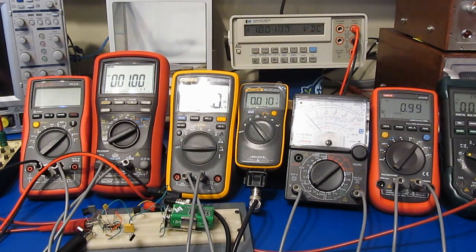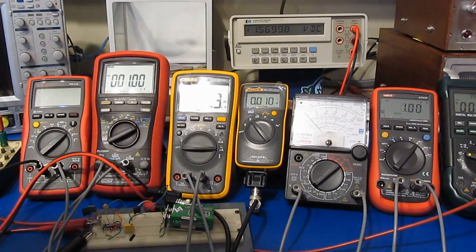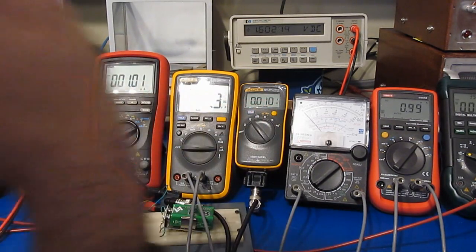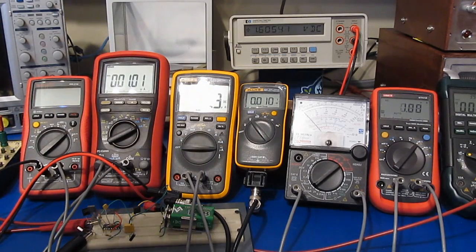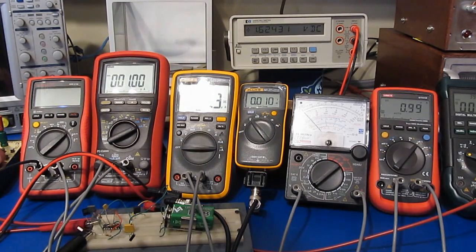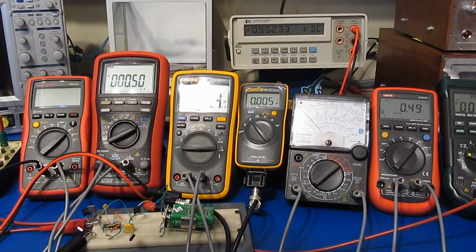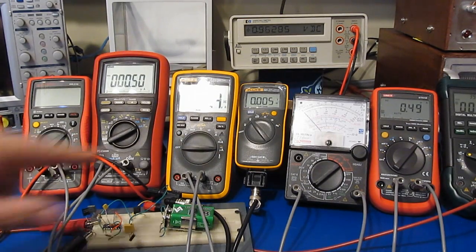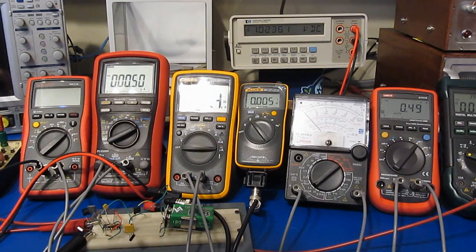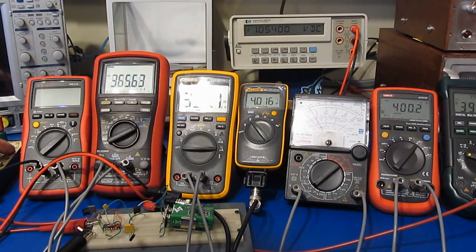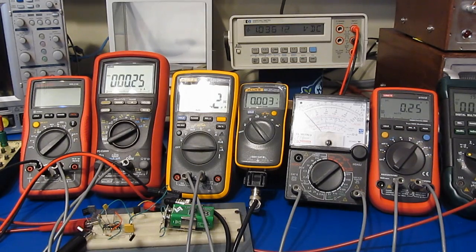I'll just go ahead and adjust the current down to 1 microamp. And again this is multiplied by 10. So you can see it's roughly 10 millivolts right now. Go a little bit lower. Let's halve it again. This will be roughly 500 nanoamps. We'll halve it again. So this will be 250 nanoamps.